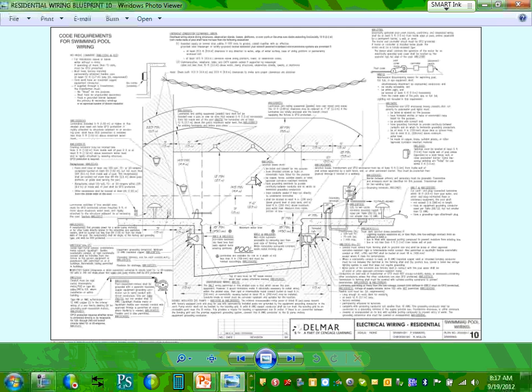To recap what we've done, you need at least one receptacle, guys, for a swimming pool, not closer than 6 feet, not further than 20 feet, GFCI. Can you have a check, Chad, for that one? Your lights, move your lights away 5 feet from the swimming pool and GFCI them. If you put them, GFCI them. Your pump, if it's 20 amp, 120 and 240, which in our case it will be, you're going to GFCI your pump, right? So what do you do? You put a 2-pole GFCI circuit breaker, feed it to the pump. You have to have a disconnect for the pump, not closer than 5 feet from the inside of the pool. So make sure you put the disconnect not closer than 5 feet. You disconnect the pump, and the pump will be GFCI'd if it's 120 or 240 or 208, 15 or 20 amp circuit, right?